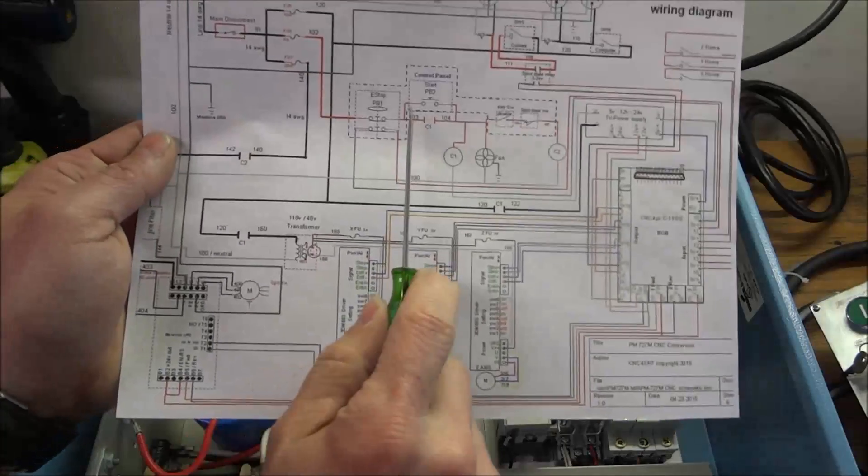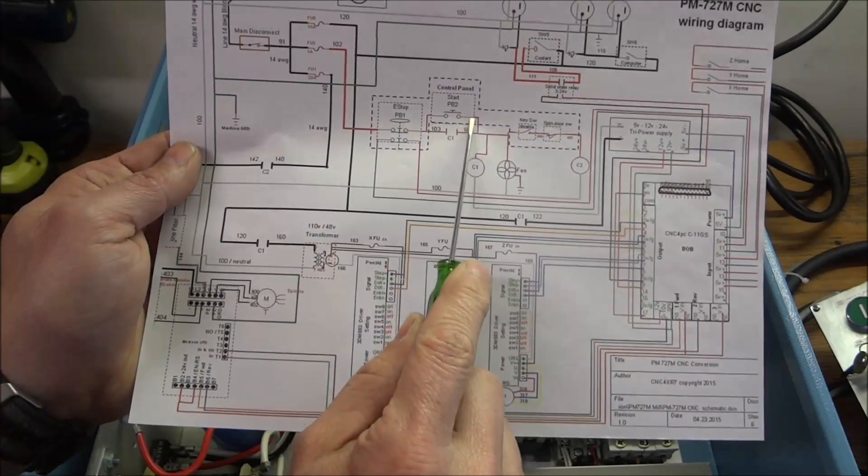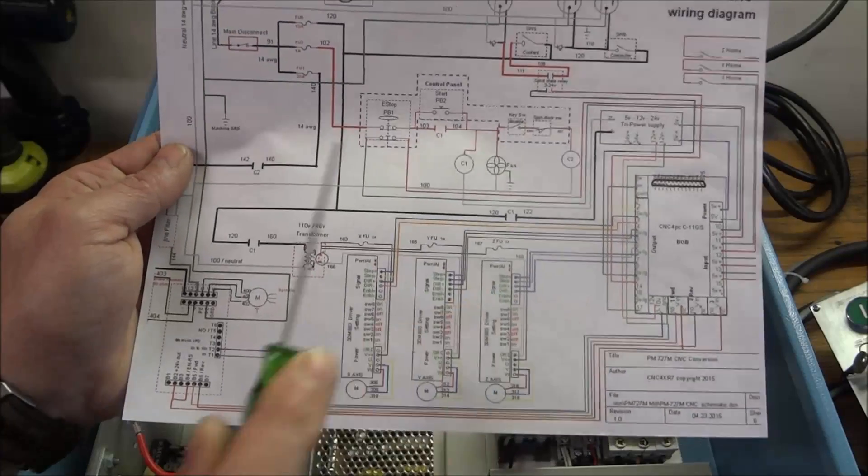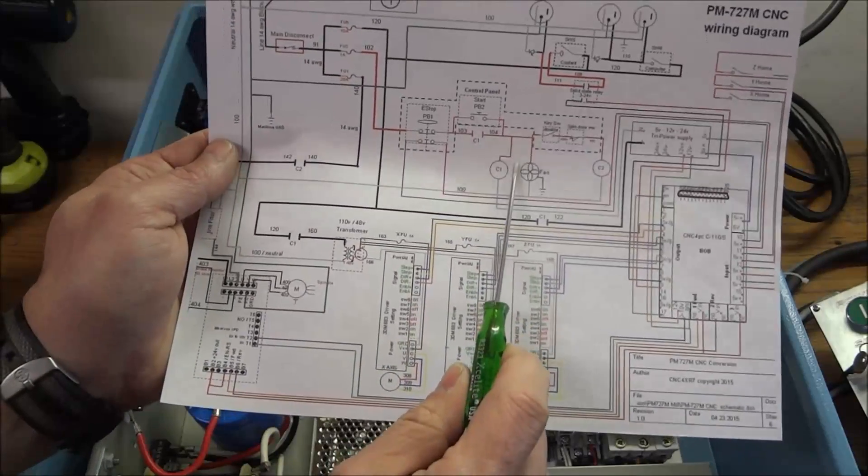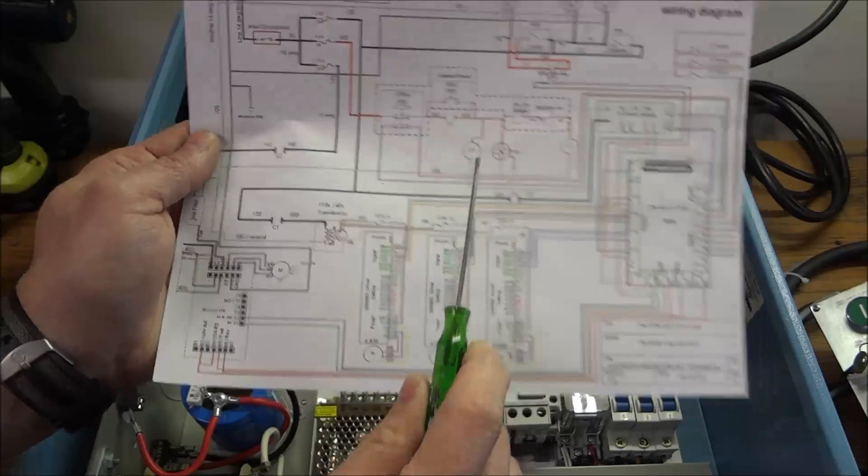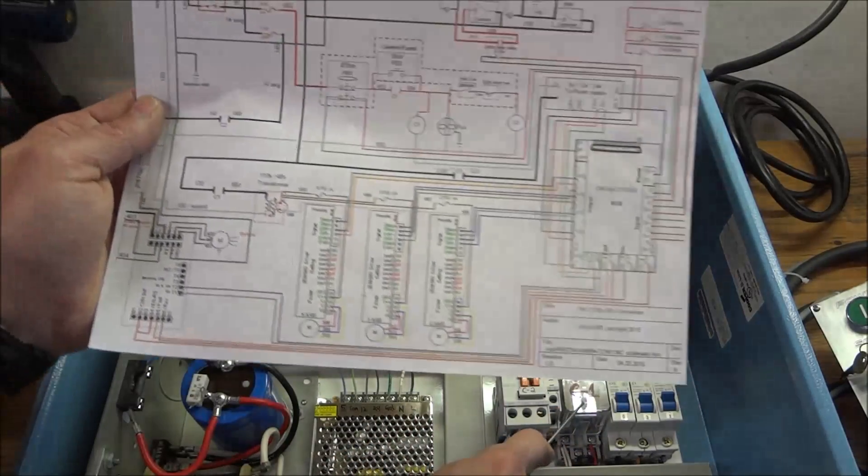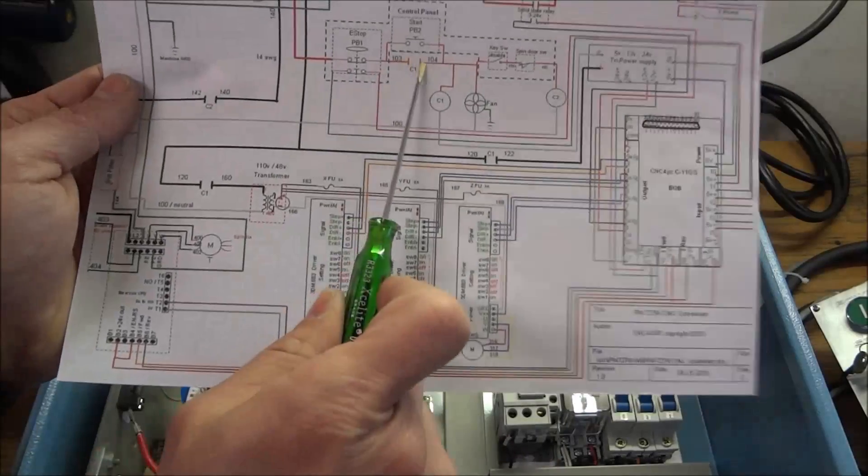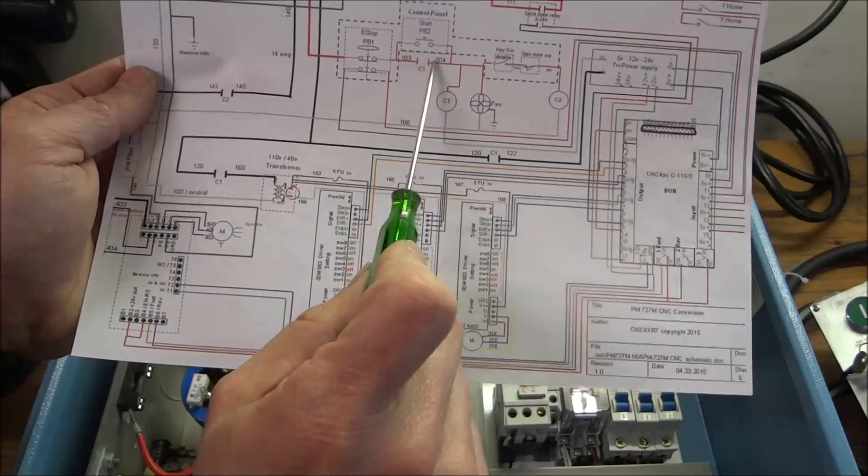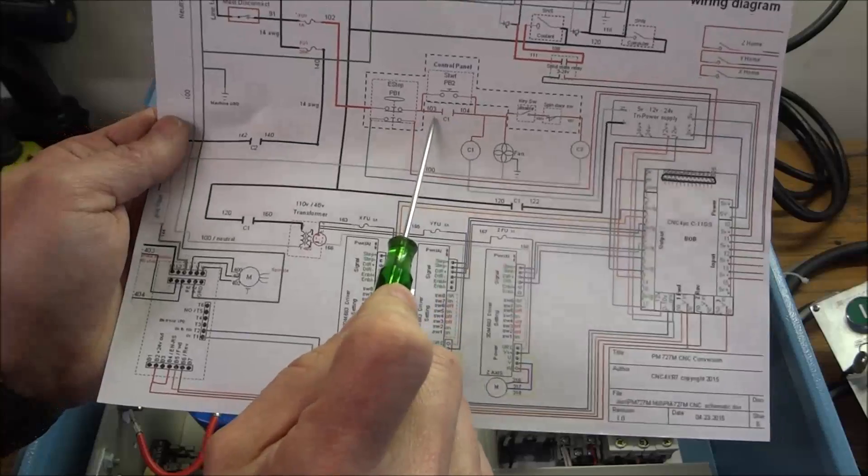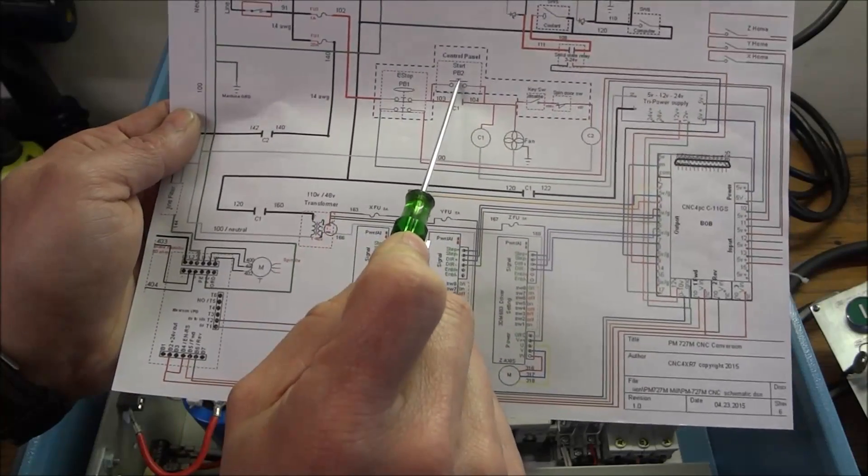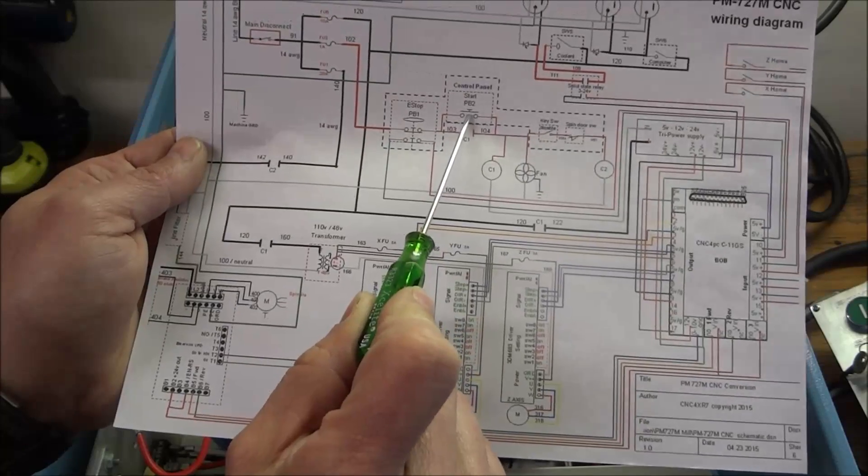Now once we press the power on button, 110 volts will go through the button momentarily as long as the button is pressed. And power will be applied to our C1 relay coil. Once that coil is energized, it will close these sets of contacts right here. These are our holding contacts.